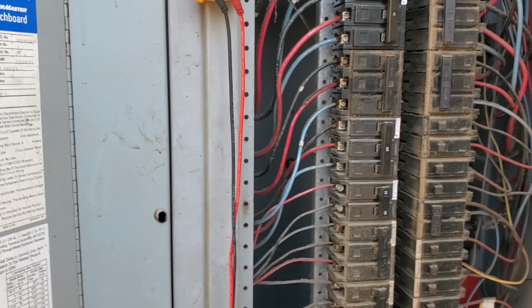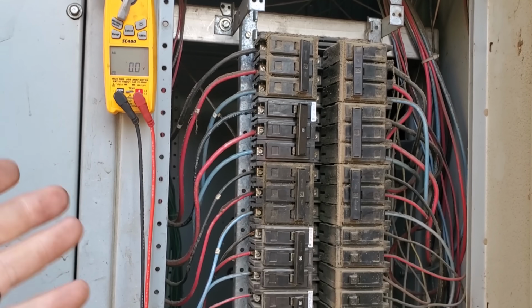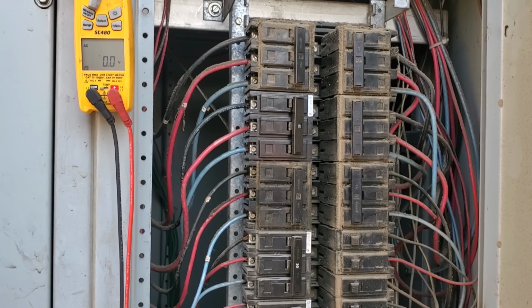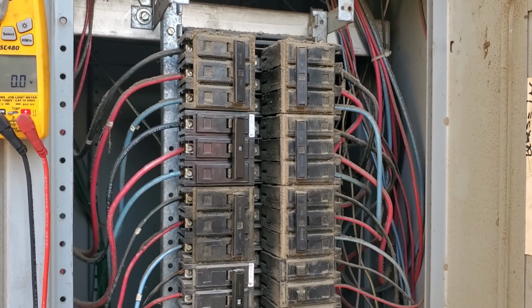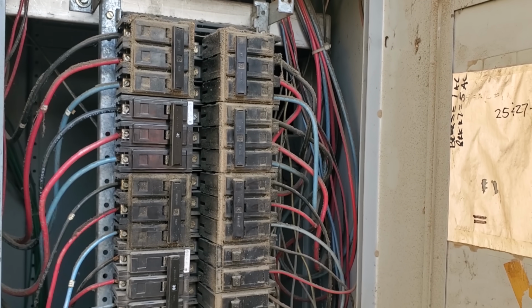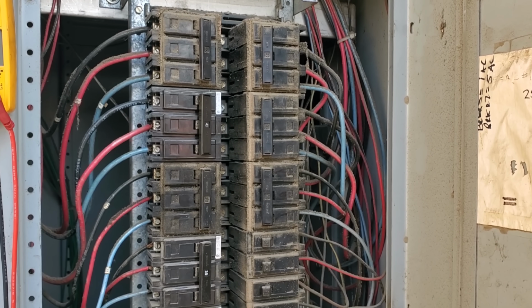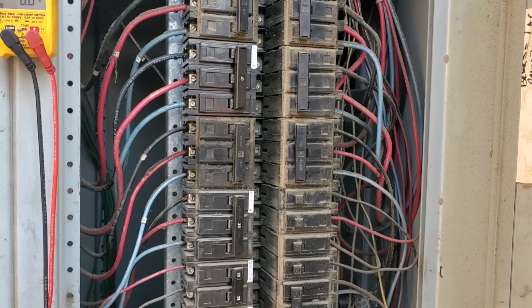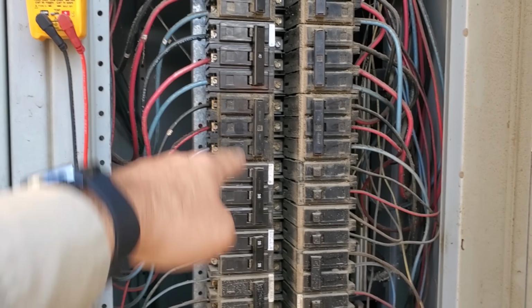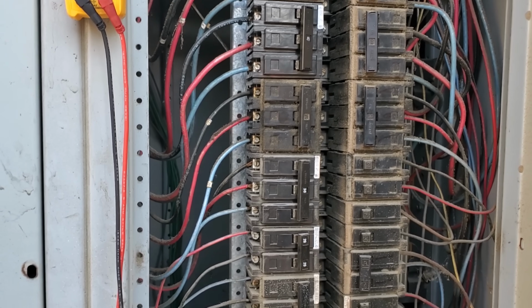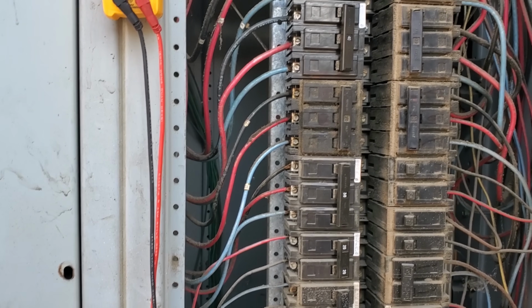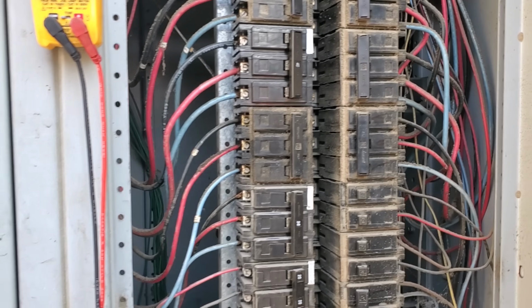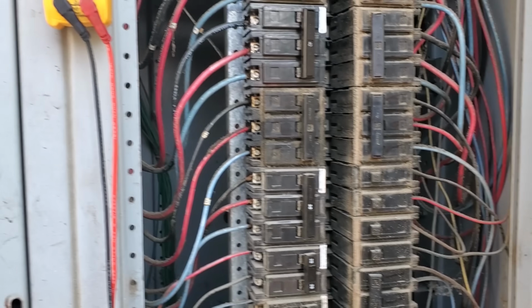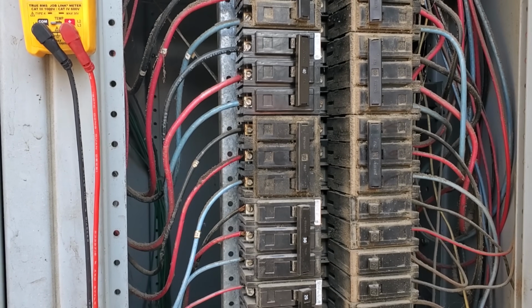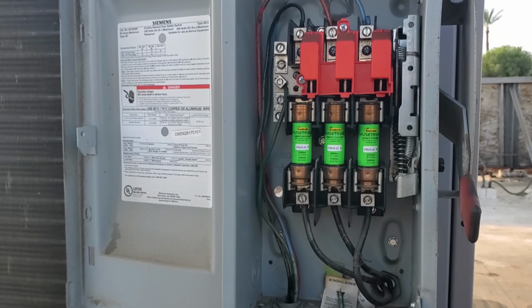We're gonna go ahead and put the panel back together, and then we'll reset it. I don't wanna reset it with it off just in case it blows up or something. So we're gonna put that on, reset it, see if we can get it to reset real quick. And then we'll have to get an electrician to change this. I also would like to see that breaker go up in size if there's room, although that wire's only 10 gauge because there's 45 amp fuses in the unit and it's only a 30 amp breaker, but it's minimum 30, maximum 45.